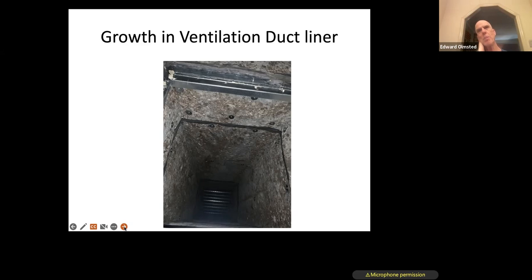And so, over designing it. And what happened here is it was very cold air and it was humid air. And that's the lining. The second thing they did badly in this building is they have a lining of their ducts right inside the ducts. Nobody does that and should be doing that anymore. The ducts should be insulated on the outside. Duct lining is something to avoid. So here, this was a fairly new building, and all the ducts are lined, and they all grew out mold, and so now, in a 3-year-old building, they have to tear out all these ducts, every duct, and put in new duct.